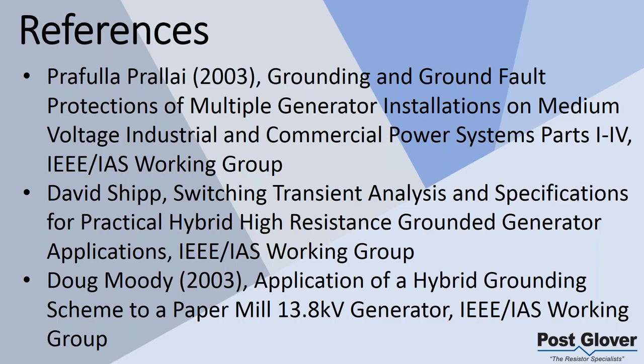So you're going to have to trip on a low resistance ground system, whereas on a high resistance ground system, not necessarily. You're going to continue to operate on a lot of different applications. You're going to continue to operate with faults.